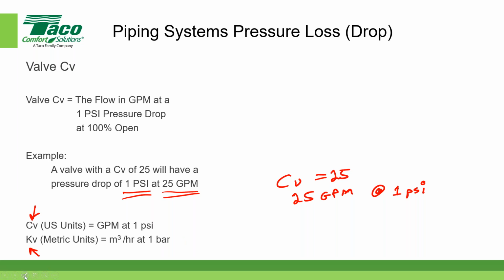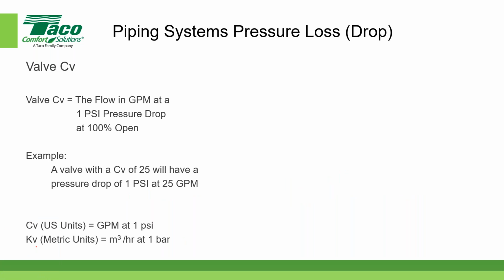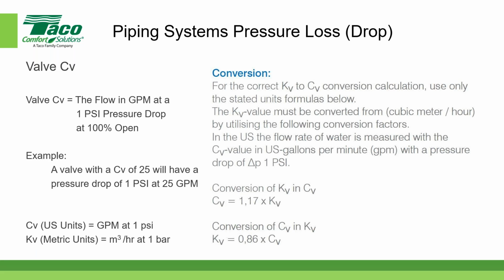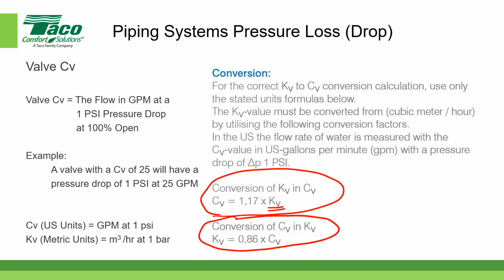And I have a little paragraph over here. I'm not going to read the whole thing, but basically these are the conversions. If you are looking for the CV and you've been given the metric value, if you multiply by 1.17, you can convert that into a CV value. If it happens to be a CV value and you want it in the KV metric system, you would take the CV value multiplied by 0.86. So that's a couple of conversions that might be of value to you.